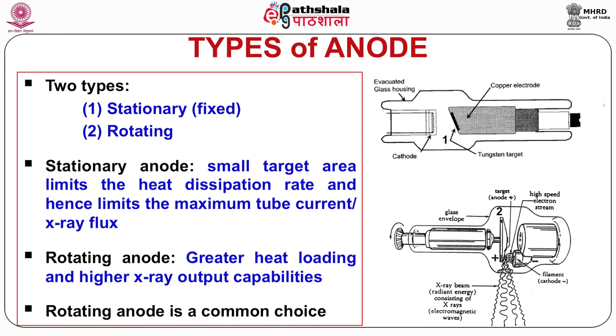There are two types of anodes used in medical diagnostic X-ray tubes: stationary (fixed) and rotating anodes. The simplest type has a stationary anode which consists of a tungsten insert embedded in a copper block. The copper block mechanically supports the tungsten target and removes heat efficiently due to its higher heat conductivity. However, the small target area limits the heat dissipation rate and hence limits the maximum tube current and X-ray flux. Stationary anode X-ray tubes are used in dental X-ray units, portable X-ray machines, and portable fluoroscopy systems.